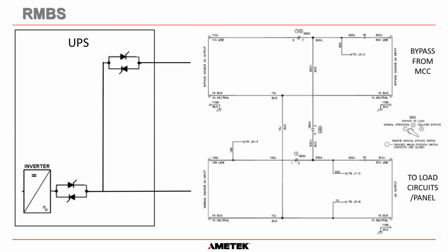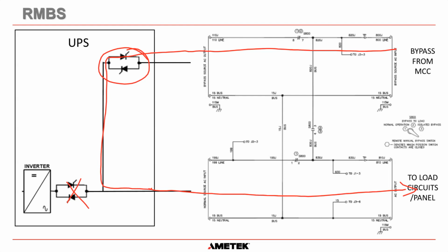Now, once again, the UPS is going to have its procedure, and you're going to be going through it here just now. So we are on inverter static switch, and the bypass static switch is going to be off. Okay. The first thing that the procedure is going to do is tell you to press the bypass to load push button. That turns this static switch on and turns this static switch off. So what will happen is bypass will flow through here, down, still inside the UPS. So we still have power and voltage inside the UPS. It will come out here, come through here, and go out to your load circuits. Okay?